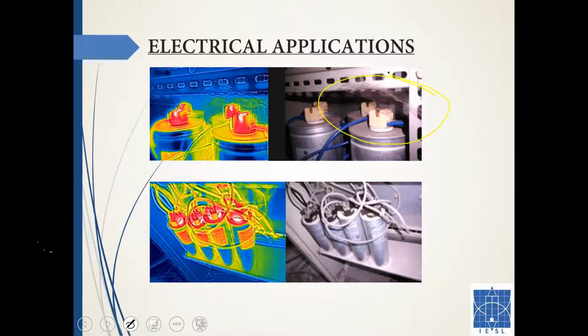Capacitors are kind of delicate devices, right? They don't tolerate harsh environments. When the manufacturer says it's 40 degrees ambient, you need to think that it's 30, right? You need to keep them air conditioned. You need to pay close attention. If not, I have seen these hotspots get around 150 degrees really easily, right? You need to maintain these capacitor banks and do the regular maintenance. During a shutdown, you need to measure the capacitance value through the terminals and make sure that the capacitances are in good shape.